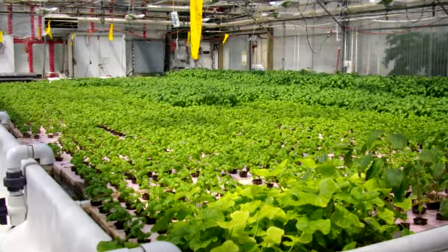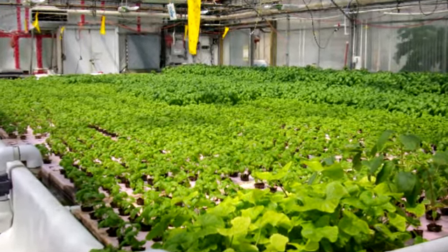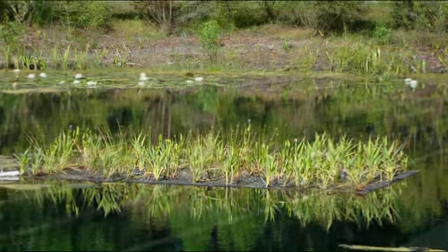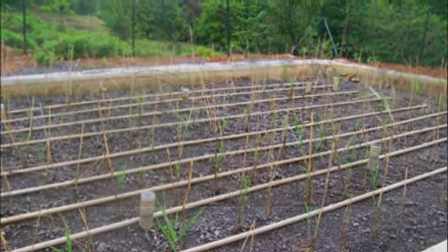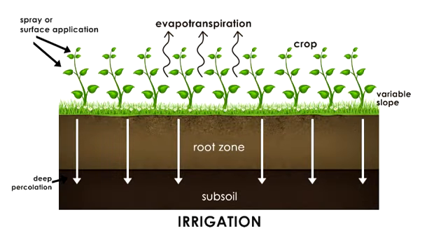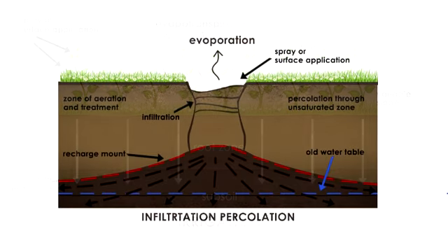In general, natural wastewater treatment systems are divided into four broad types: terrestrial treatment methods, wastewater stabilization ponds, aquatic plant systems, and constructed systems. Terrestrial treatment methods depend on the physical, chemical, and biological reactions on and within the soil matrix. The wastewater, after a preliminary treatment step, is disposed on the soil. Technologies comprise slow-rate, rapid infiltration, and overland flow systems, as well as combinations of these types. In slow-rate and overland flow methods, vegetation constitutes a significant treatment component, while in rapid infiltration, vegetation is not necessary.